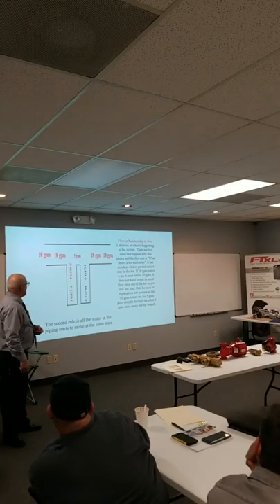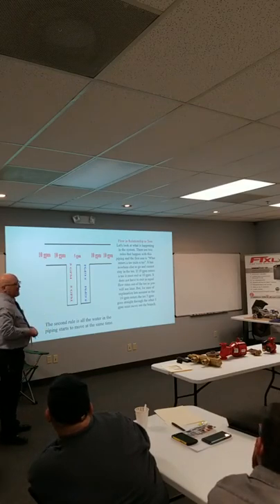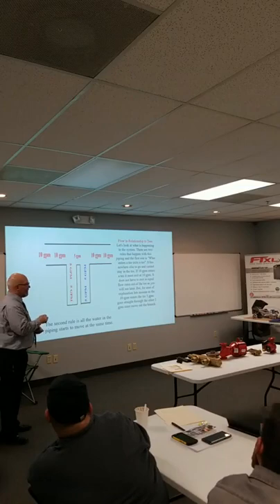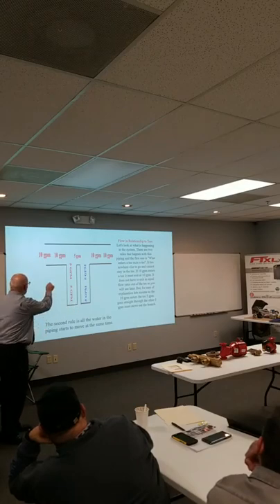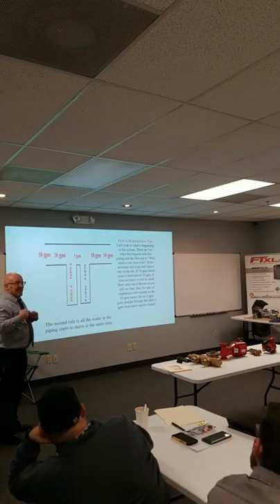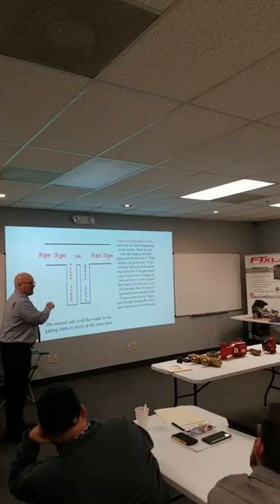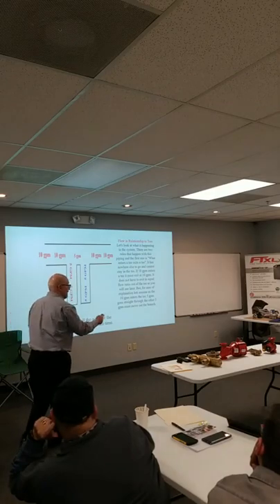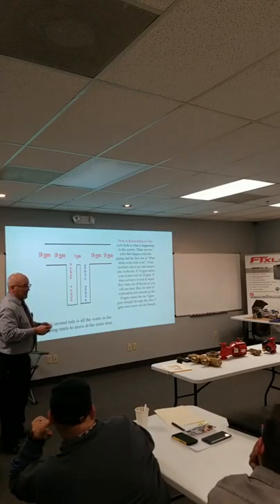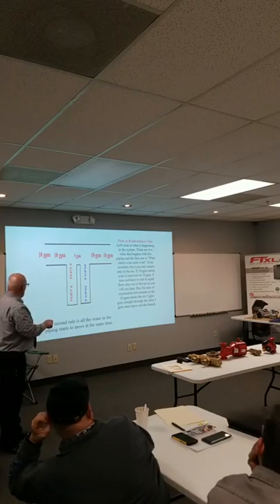Okay, so here's what happens inside of a primary secondary loop. Real quick, I want to go over a couple slides. So I've got 10 gallons a minute going through the system. This is my boiler loop. This is smaller piping than that. What is this loop? Secondary. Nice. What is this loop? Primary. Boiler loop, system loop. I really don't care at that point. But you get my point. It is different and it can change. That's why I don't like using the term primary, secondary. So we got 5 gallons a minute coming back.